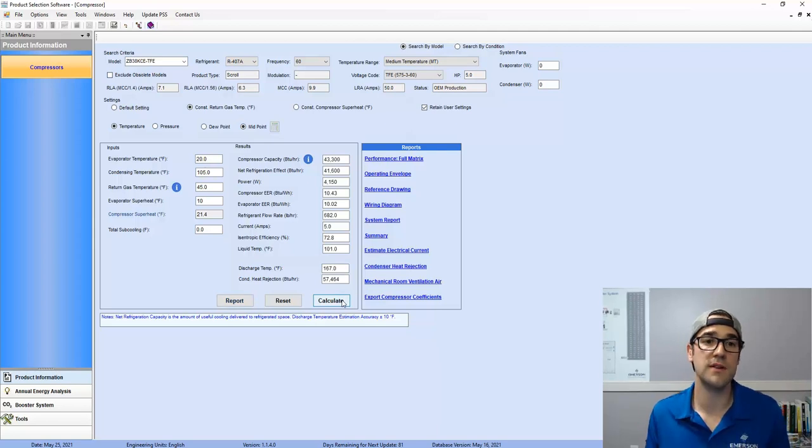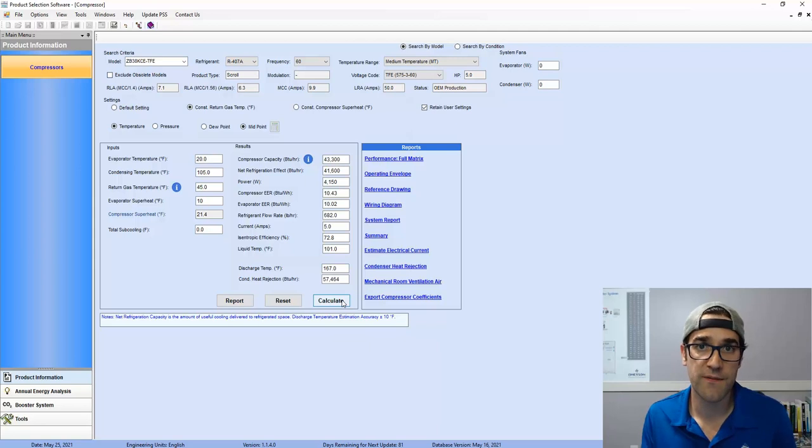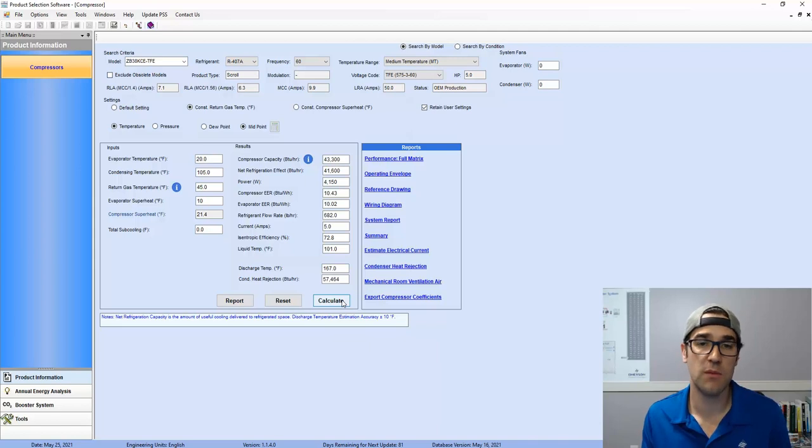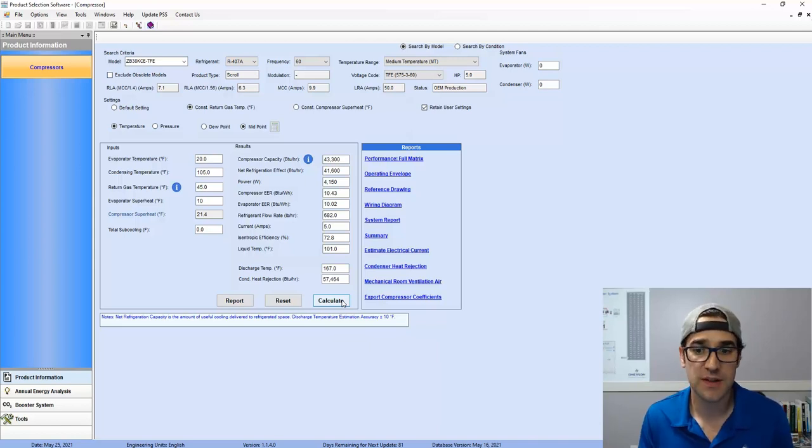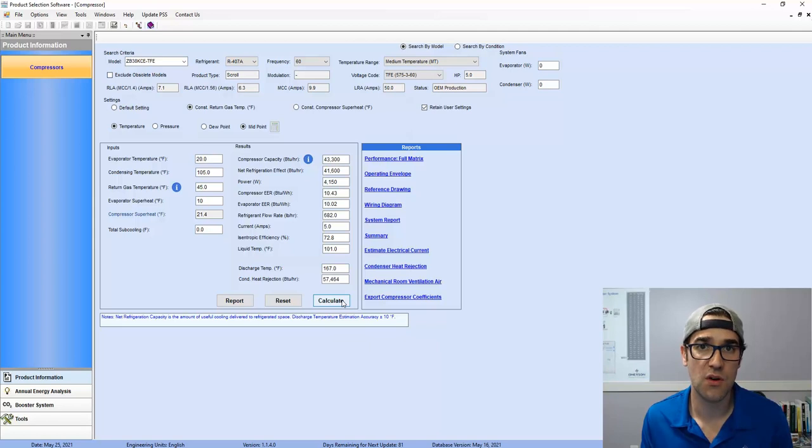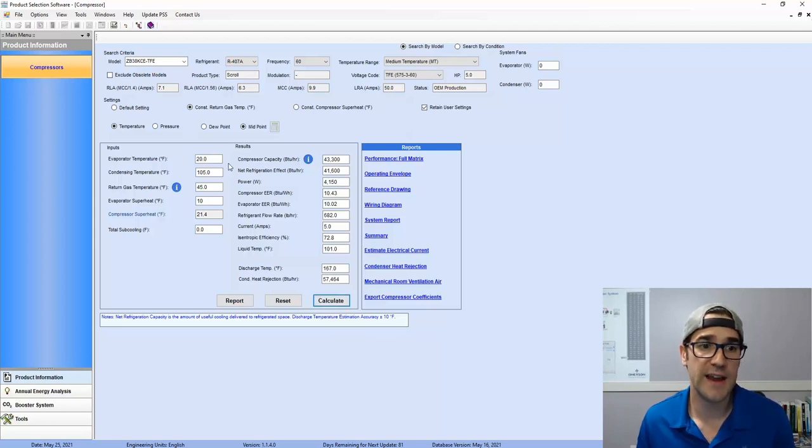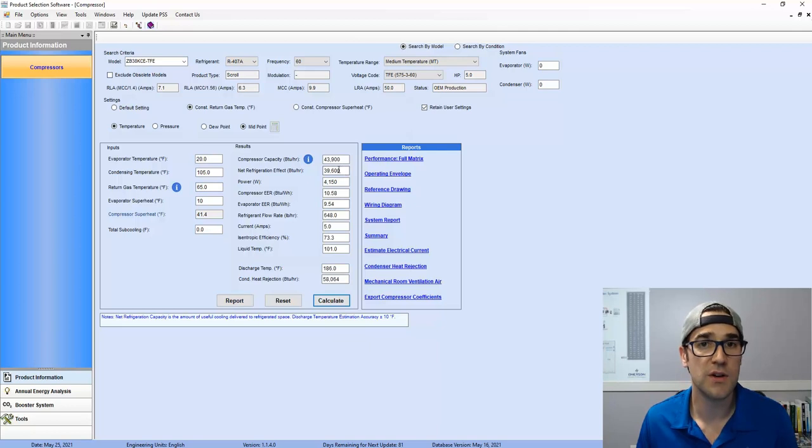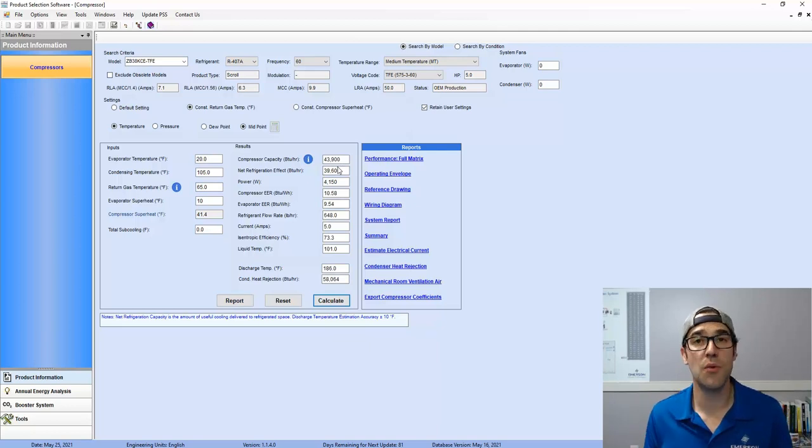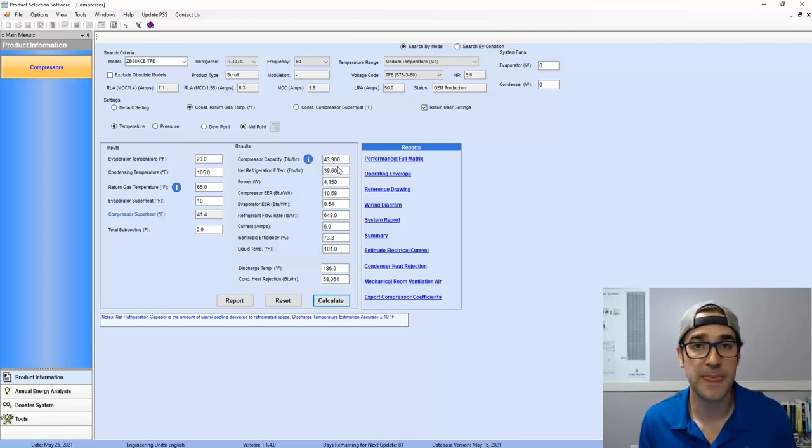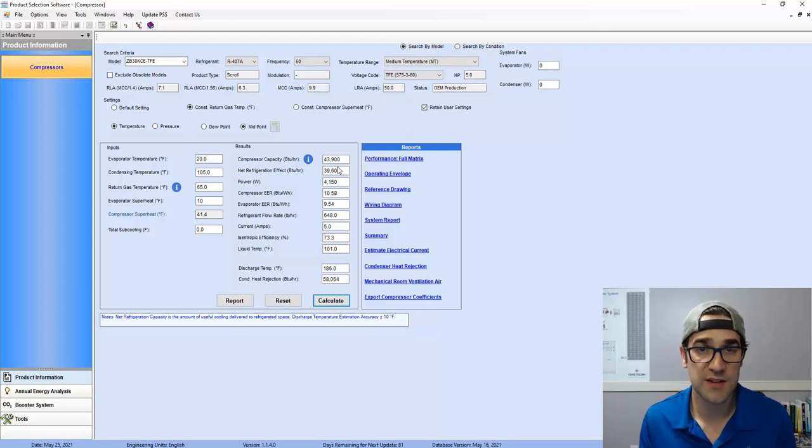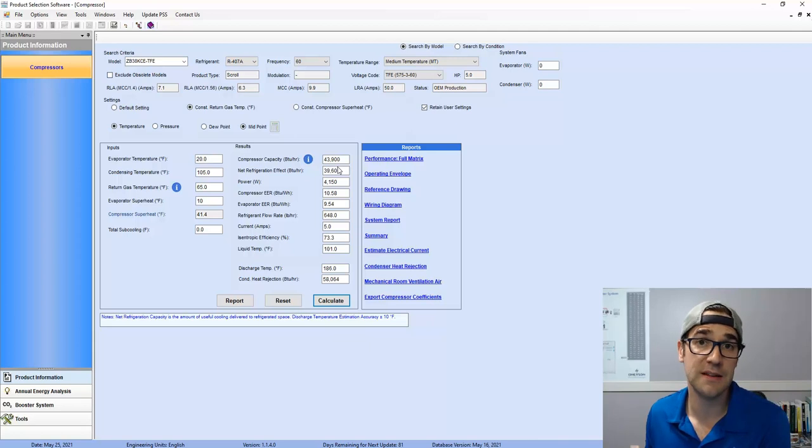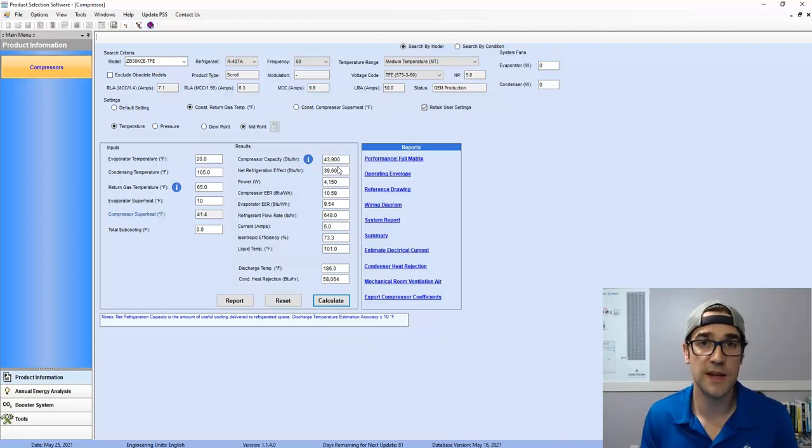So now, as you can see here, we're meeting our 40,000 BTU requirement with 41.6. That's probably 4%, 4 or 5% oversize, which is a great ratio. That is with a 45 degree return gas. Now, if I turn this back to 65, we're not reaching that 40,000 BTU. So it's vitally important that the conditions that you design the compressors or the system at, that that exact same conditions are happening in the field to make sure you maintain your proper temperature.